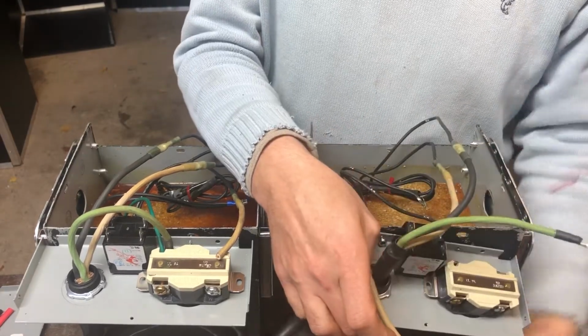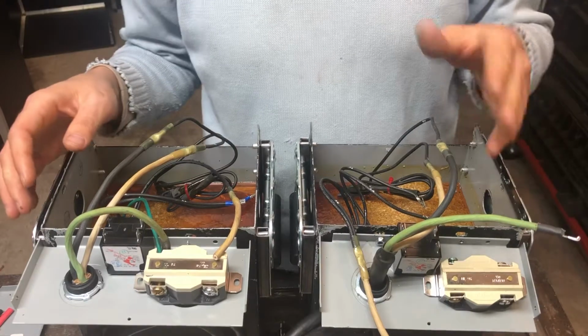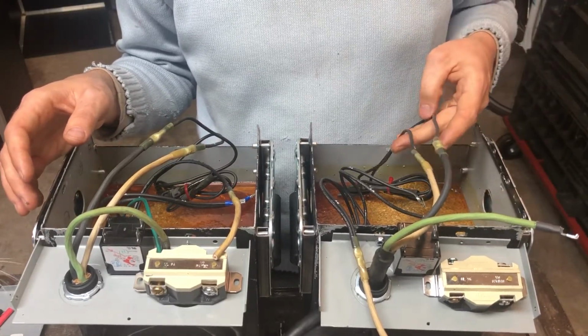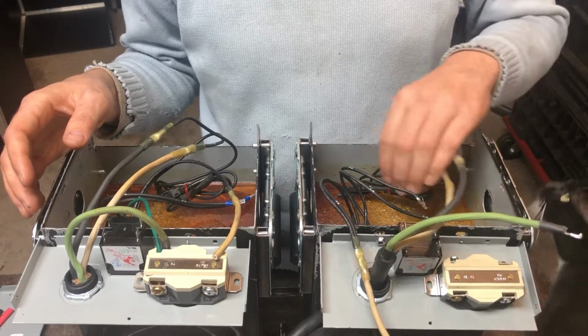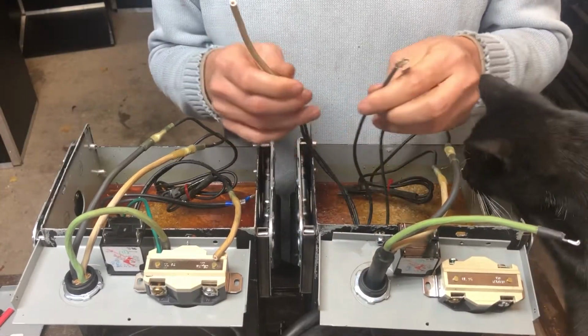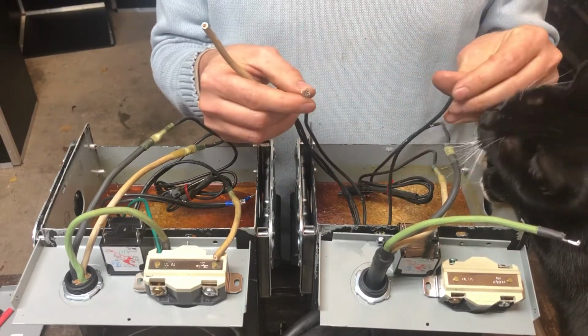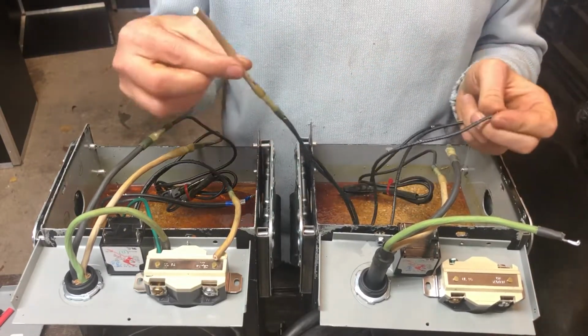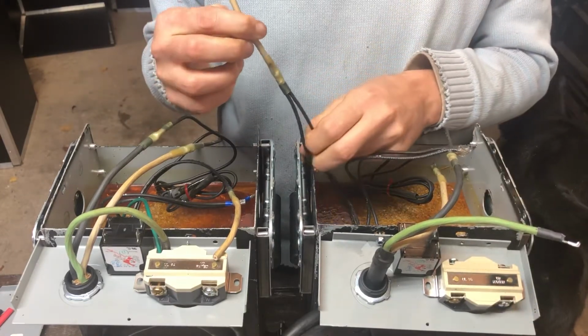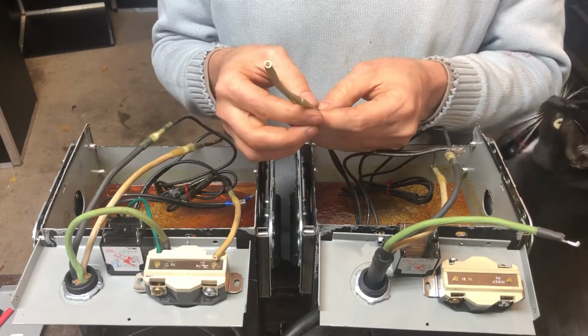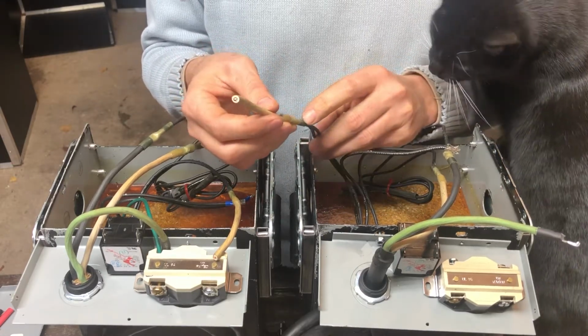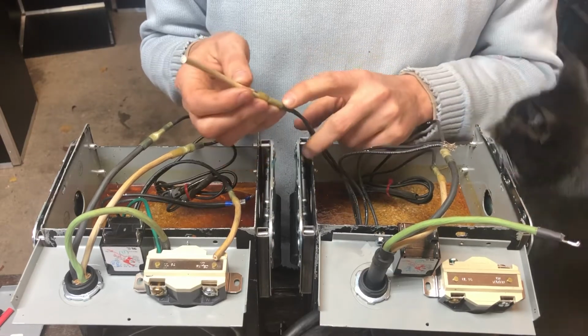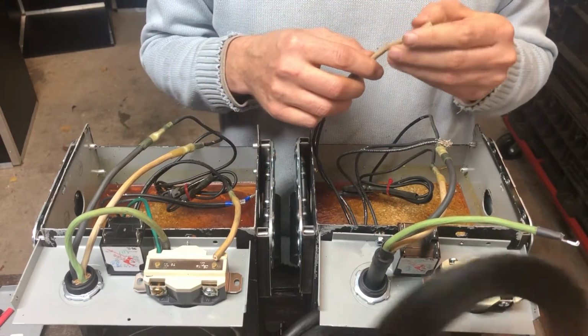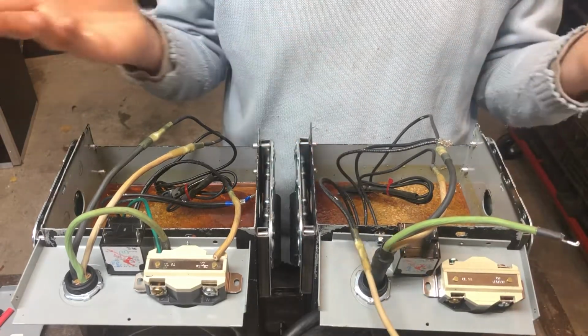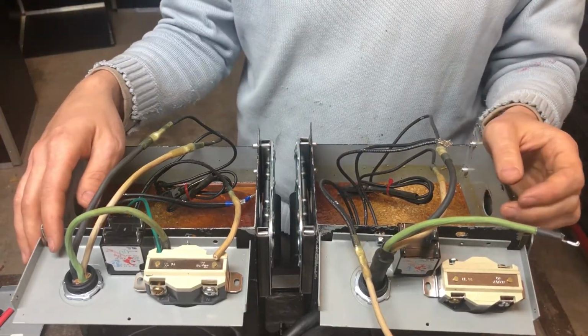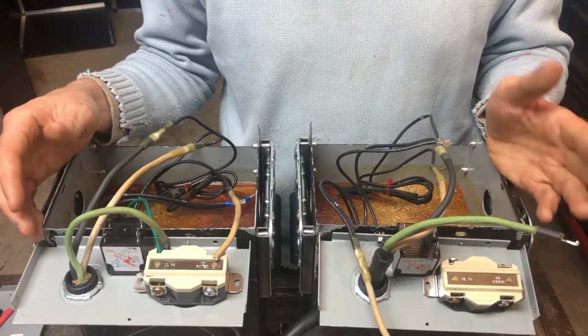So my 277 comes in here, and it goes into the taps for the 277 input, and then my output is these three things: one of the phases, the other phase, and the center tap. You can see the center tap has two wires in it because that's how you get the center tap. If you were just going to have the 240 volt version, you would just connect these two together, and you wouldn't need to tie on a neutral for center tap stuff. I think foreigners call that split phase, for the way the United States does it.